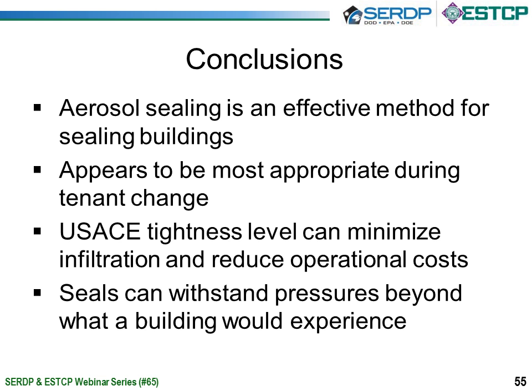We also found through our modeling that the USACE tightness level can minimize infiltration. I forgot to mention this before, but buildings that require some type of pressurization target really require more air to pressurize the building than is required for ventilation. So that's an additional energy benefit. If the building has a pressurization target that you're trying to meet, you can reduce the amount of air required for pressurization down to basically the minimum ventilation rate. And the tightness level that USACE has specified is enough that that ventilation is going to pressurize that building by itself without additional outdoor air.